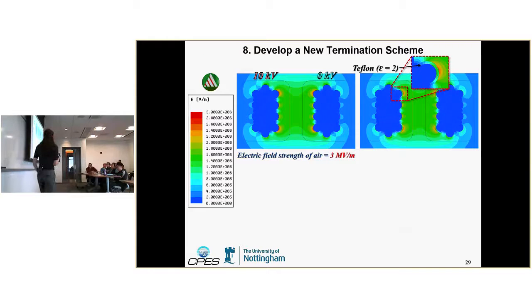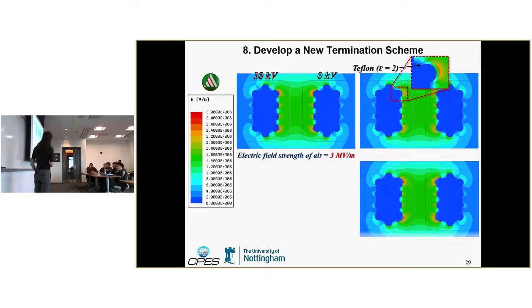What if you coat these springs with a dielectric material? Using something like Teflon with low permittivity close to that of air gives some reduction in the electric field in the air. But you need to be careful - using a dielectric like silicone with higher permittivity has almost no impact, since it won't drop much of the electric field, which then remains mostly in the air.